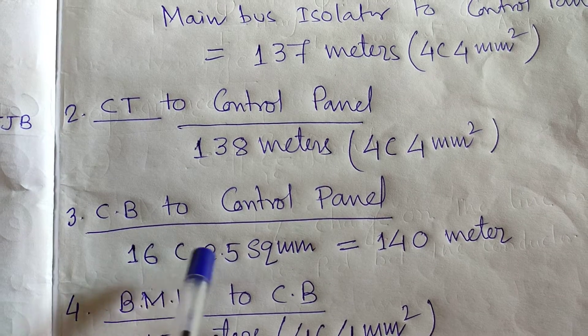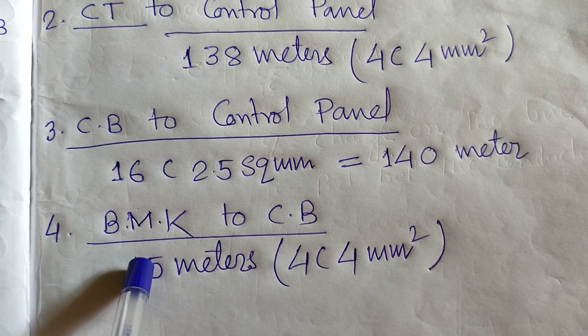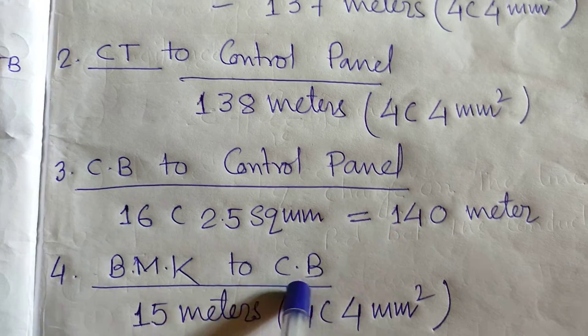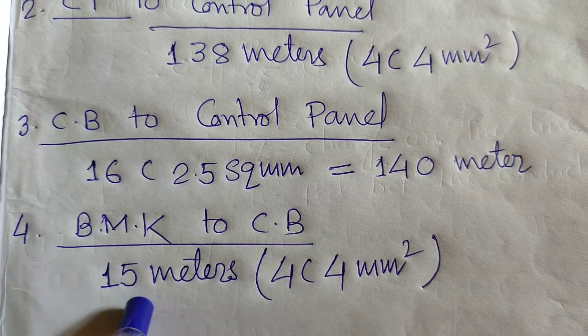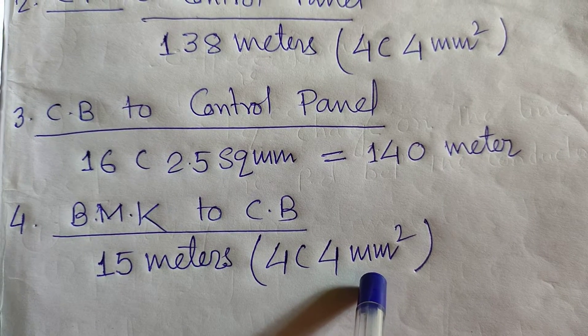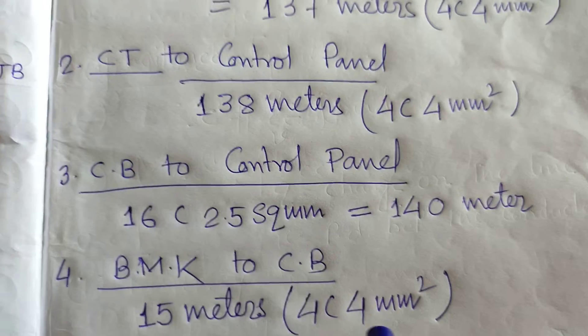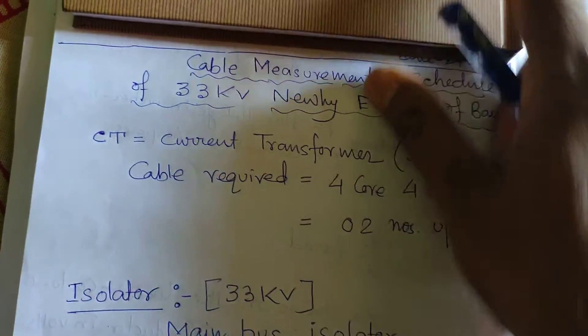From the BMK — Bay Marshalling Kiosk — to the circuit breaker: only 15 meters required because the BMK is present nearby. Here, four-core 4 sq mm cable is required for taking the AC supply for the illumination, spring charging AC motors, and space heaters. So we discussed today about the cable measurement and schedule of the 33 KV new erection bay.